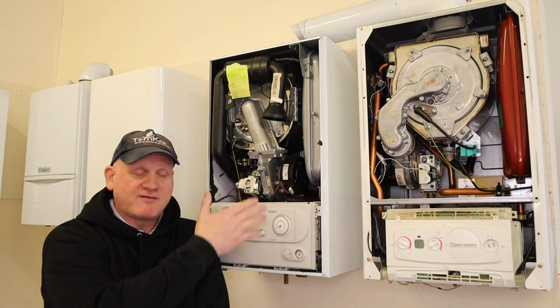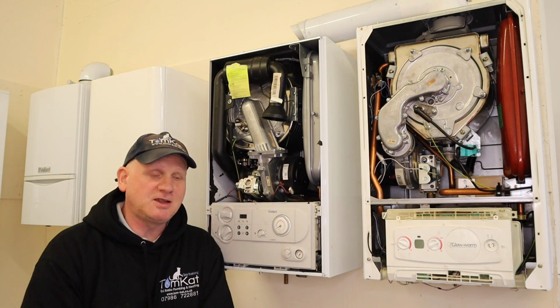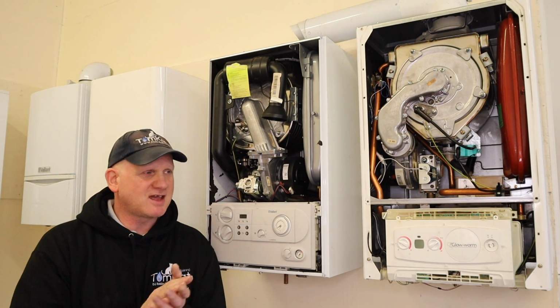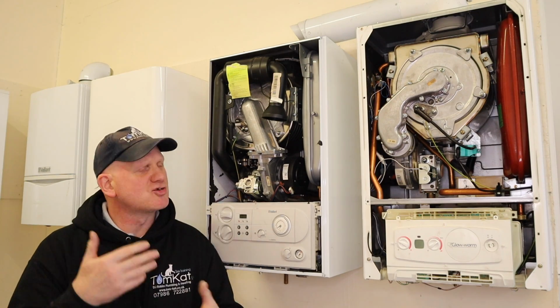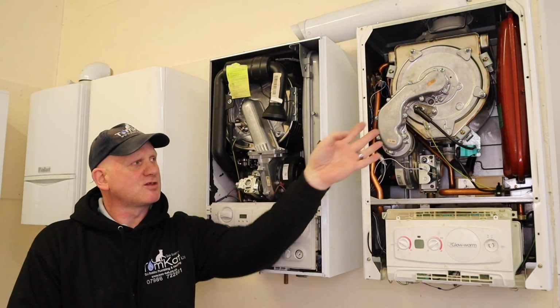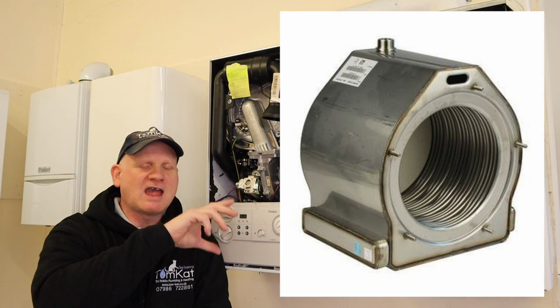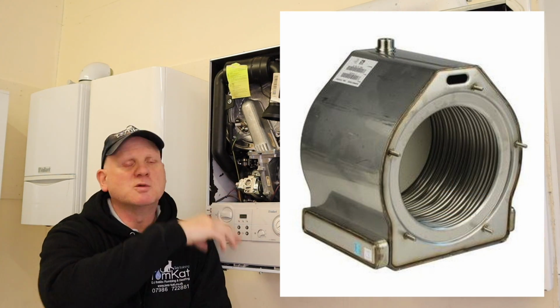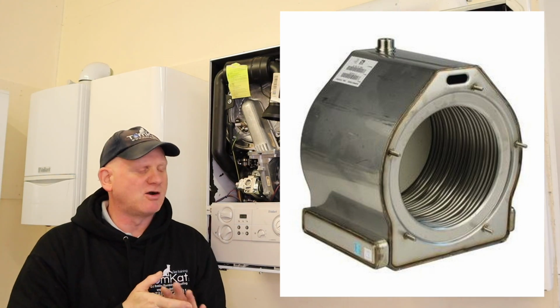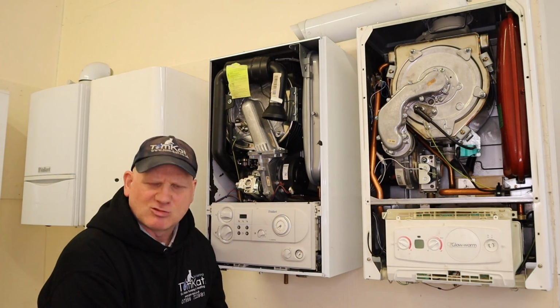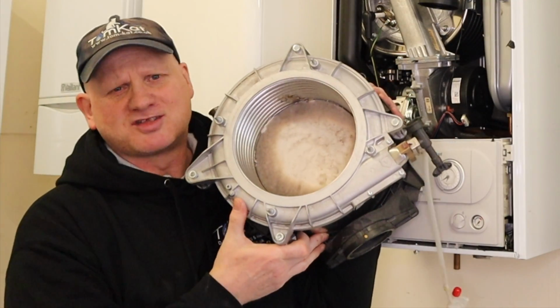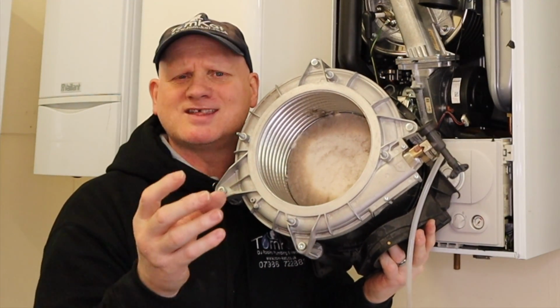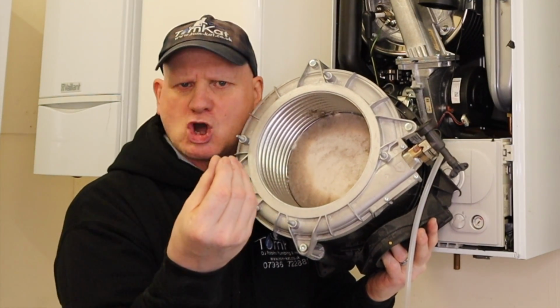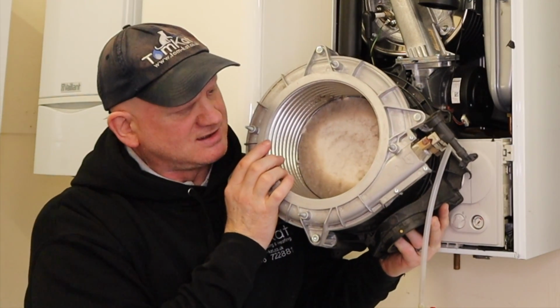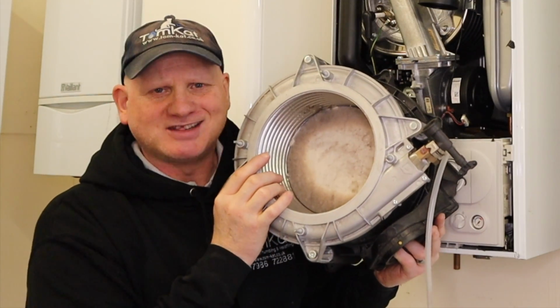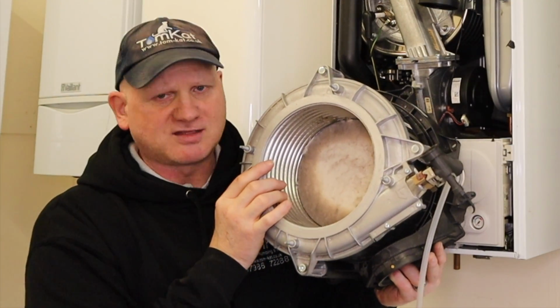The two boilers we have here both have stainless steel heat exchangers. And stainless steel heat exchangers over the years have made a progression. When these first came out, especially this one, it had 10mm coils of stainless steel and 2 passes. And that's changed now with a lot of the manufacturers. I'll pick this one up because it's heavy. They've gone to this system where it's a 28mm piece of pipe squashed into one continuous piece.